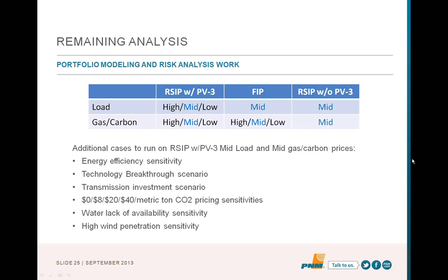Okay, the question is if we've looked at sensitivity around how many megawatts of Palo Verde 3 we would include in the portfolio, and what we've seen in terms of benefit to overall cost, risk, that type of thing, that, frankly, if Palo Verde 3 was bigger than 134, that would be what we'd be looking at. So with San Juan, we're looking at replacing 340 megawatts of baseload capacity. We happen to have an opportunity with 134 megawatts of baseload capacity at Palo Verde 3. So that doesn't get us the full replacement. One of the reasons the SIP's better than the FIP is we don't have to replace baseload one-for-one. So yeah, you're right, there might be an optimal mix there. But what I'm saying is with the benefit we've seen to the portfolio at 134, it's more likely that we would want more than 134 than less.